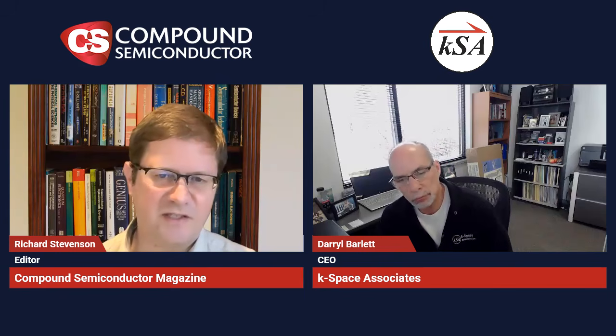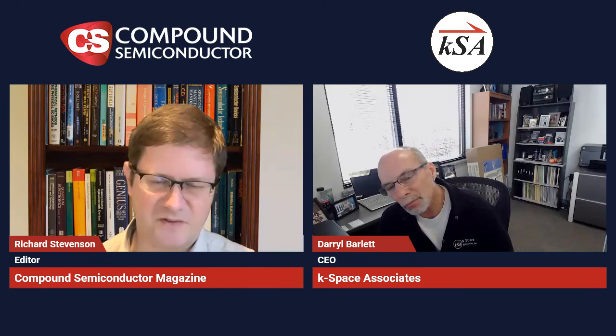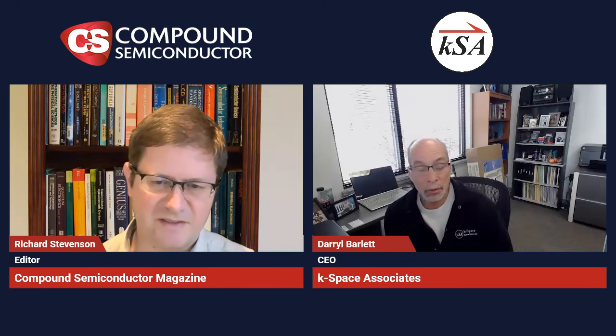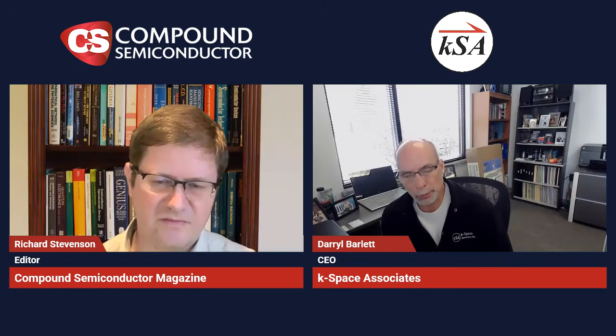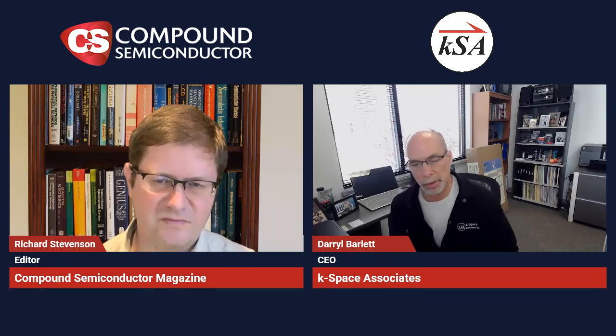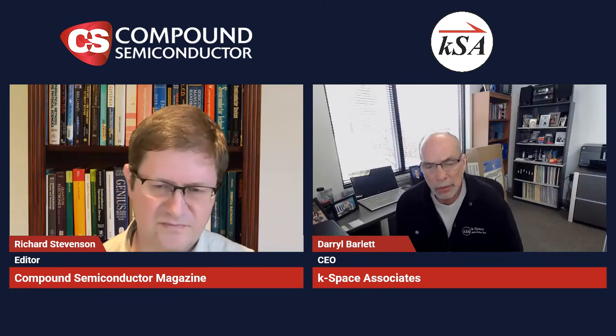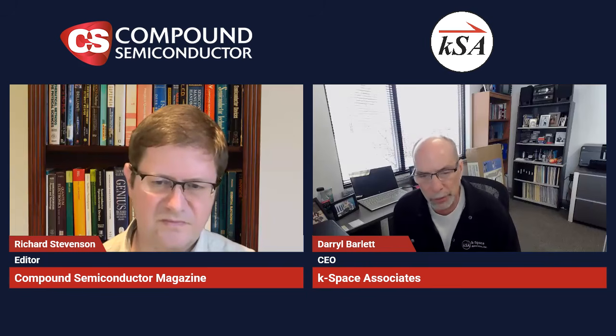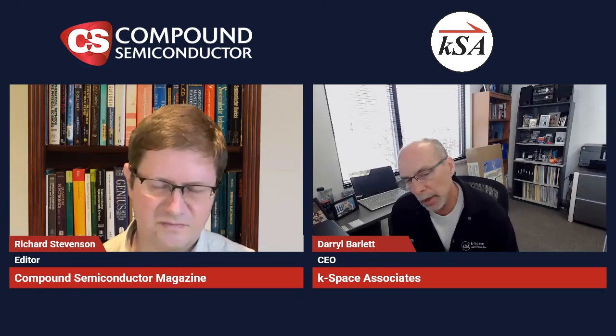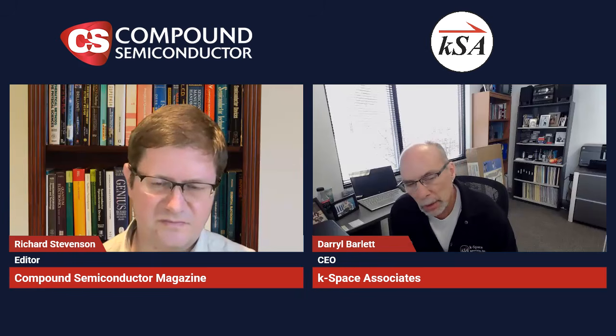Thank you. What do you consider to be the most important instruments for in situ monitoring? That's a really good question. A lot of important parameters. I would say temperature is, especially for the MBE community and probably MOCVD as well, during deposition. I'd say temperature is probably number one, right? Everything depends on your growth temperature in terms of your quality, amount of adsorption, desorption.